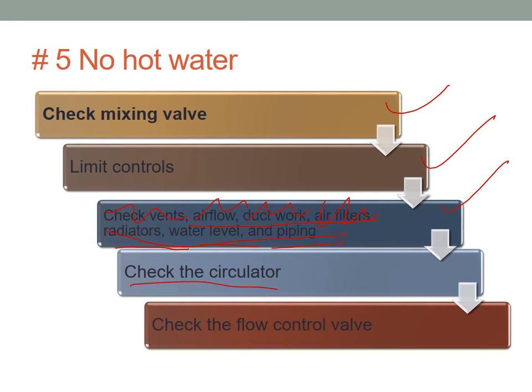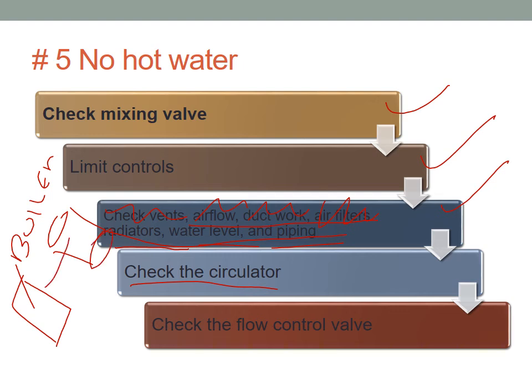Check the circulator, make sure it's actually running water, especially if we have one of this type where you have this is your boiler and this is your water tank. You could be having a circulator in here that whenever this runs low in temperature, it will circulate water back and forth. So check the circulator. Check the flow control valve, which actually controls the water coming in and out of the boiler.